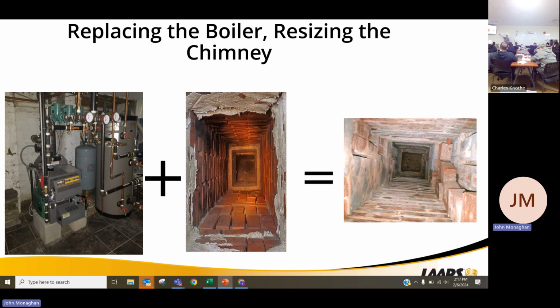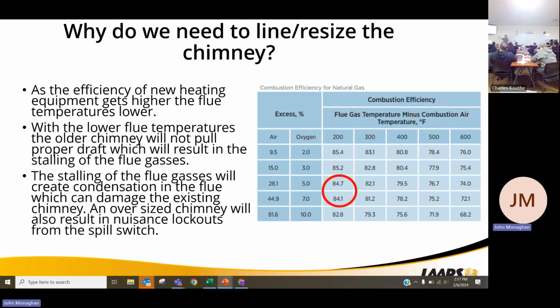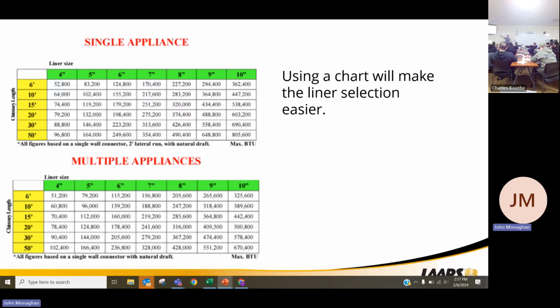That chimney, very large, usually a 6x6 or an 8x8 terracotta chimney, was designed to heat 700-800 degrees. Yes, 700 degrees of flue gas temperatures. I don't have that any longer. We're floating in turkey basting and turkey roasting temperatures. 275 to like 340 degrees is where our flue temperatures are.